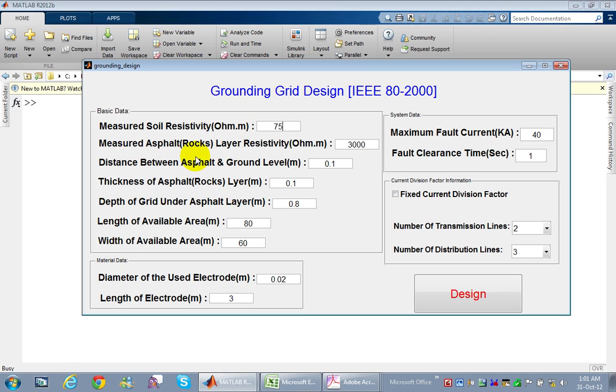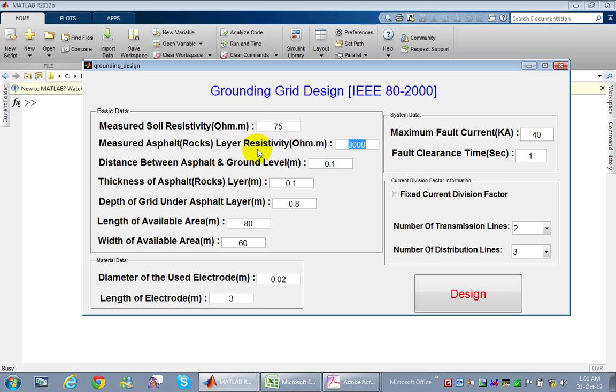We also enter the measured asphalt or rocks layer resistivity. In practice, all designers assume this to be 3000 ohm-meter based on the IEEE standard, so it can be considered a fixed value. After completing substation construction and before energization, the upper layer of the substation is usually covered with asphalt, rocks, or gravel.